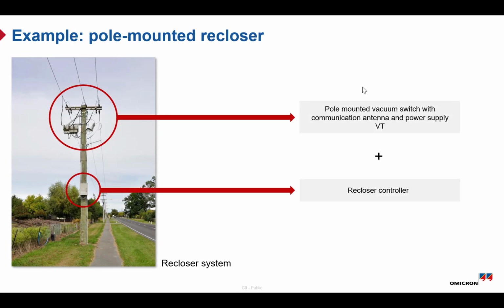Now let's look at a practical example, which is the pole-mounted recloser. In this setup, we have a vacuum switch installed on the pole. This is the device that actually opens and closes to interrupt the fault current and restore the service. You can also see a communication antenna which allows remote monitoring and control. There is also a voltage transformer, or VT, which is used for both measurement and power supply. The current and voltage signals are taken from the line and reduced to safe levels using sensors inside the unit.